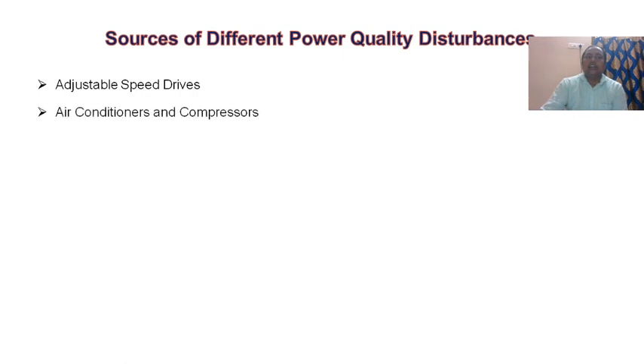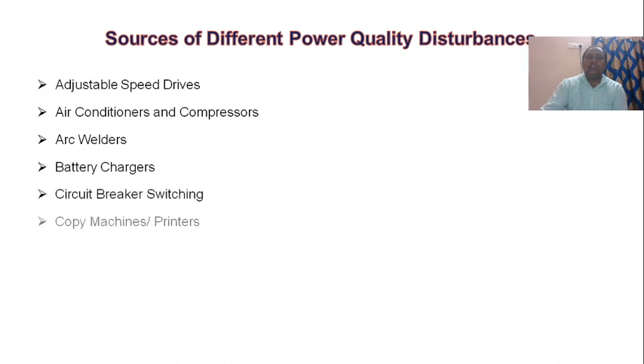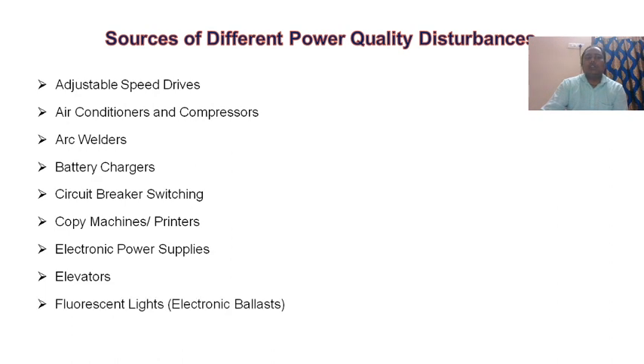Sources of different power quality disturbances are adjustable speed drives. Speed drives cause the variation in frequency that causes harmonics. Air conditioners and compressors are very inductive loads. Arc welders are very inductive loads. Inductive load causes poor power factor that causes rises in the voltage, sags and dips. Battery chargers are non-linear loads. Circuit breaker switching, sudden switching, also causes more sags, swells and interruptions. Copy machines and printers, electronic power supplies, elevators, fluorescent lights, electronic ballast.